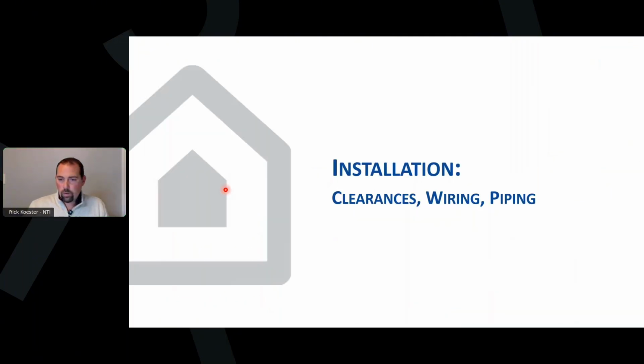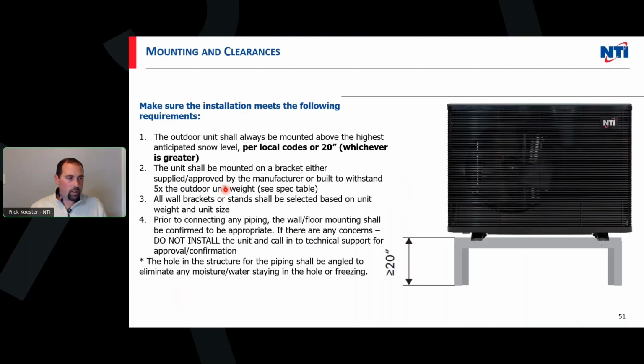All right, so taking a look at some of the installation, we're going to touch on clearances and all of those guidelines. Obviously, snow is a big part of the north up there, so we have to be mindful of where we're mounting these machines. They've got to get up above the snow load, so we like to be at least 20 inches above. The snow is an inconvenience, I like to say, and I've dealt with heat pumps for a long time. If you have this thing blocked up with snow and we lose the airflow and this thing can't turn, you're going to get an error code. It's going to shut down. It's now an inconvenience because now somebody's got to go out there and shovel it.